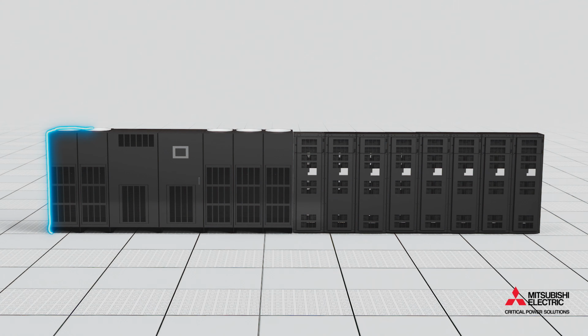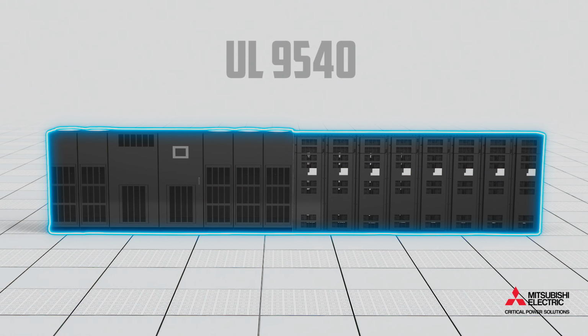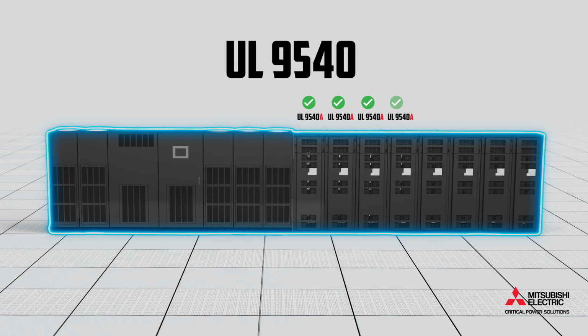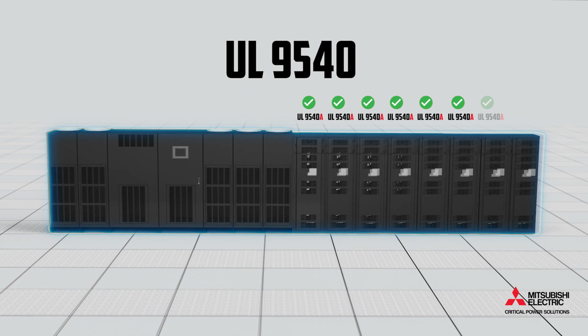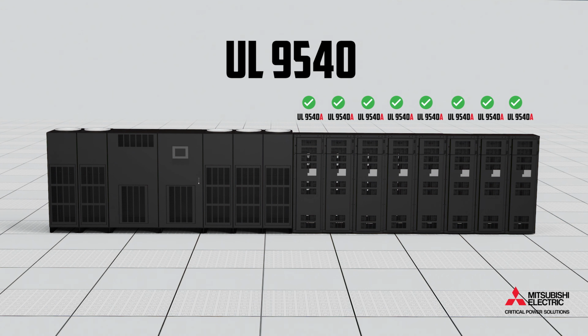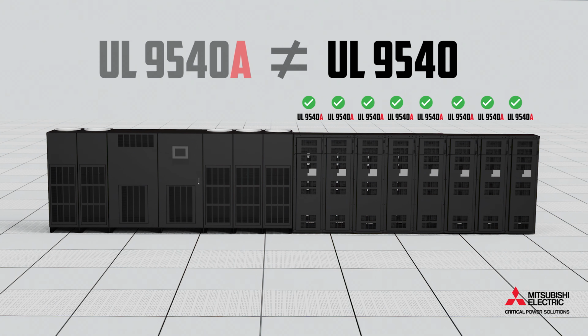UL 9540 references UL 9540A, and to meet some portions of UL 9540, an energy storage system must have acceptable UL 9540A test results. If a product has acceptable UL 9540A test results, that does not automatically mean that it will meet the requirements as a system for UL 9540 listing.